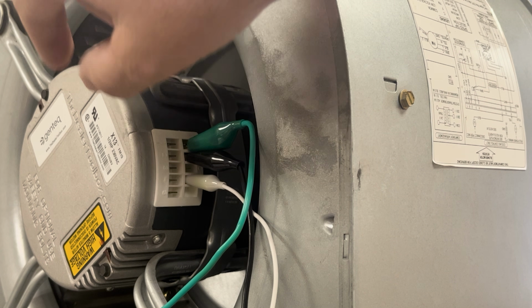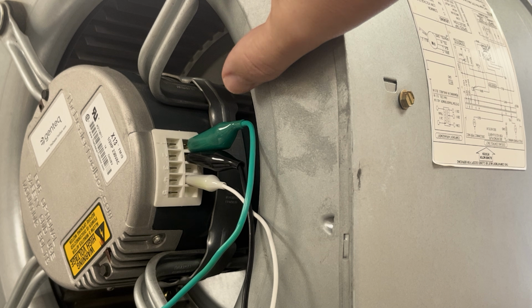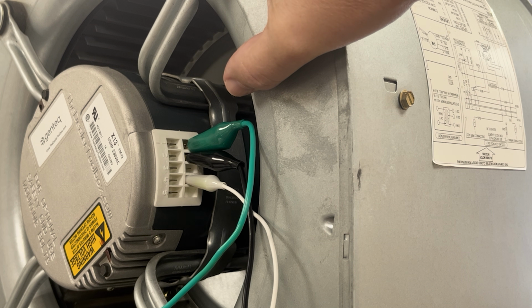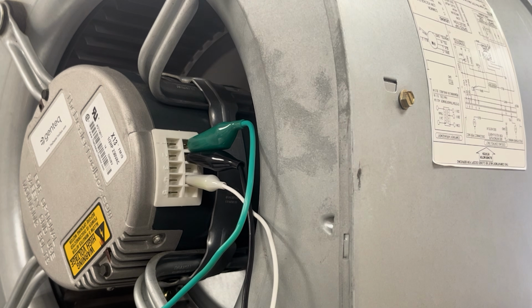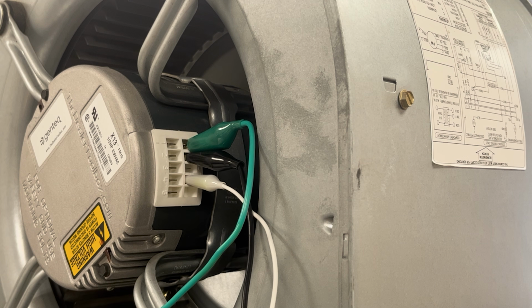And so you can simply take your blower section out, just a couple screws, unplug it. You can see here we have a yellow sticker that says warning high voltage. Allow 5 minutes after power is disconnected before opening the motor. So power is still connected up here. So we're going to go ahead and turn the power off, and it'll be 5 minutes before we do that.